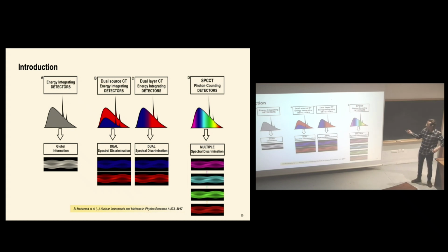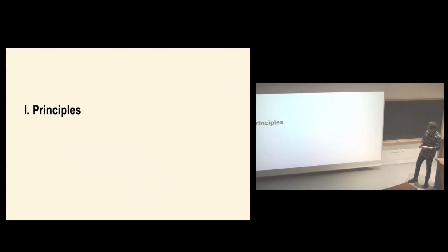This is the groundbreaking technology that I will also explain, changing from a sampling of two energy windows to an extended number of energy windows, from 4 to 8 sometimes. You will see that it gives an important power in terms of spectral discrimination, pushing one more time the limitations of conventional CT.